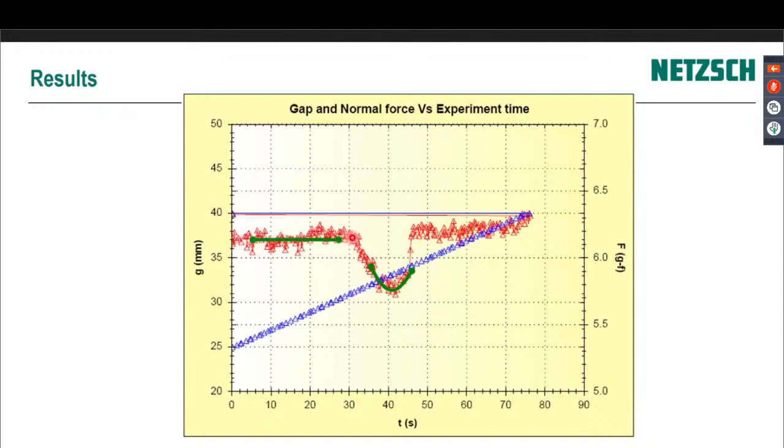And then as it lifts out of the liquid, it starts to lift a meniscus. And then it gets high enough and then it snaps. So now the Du Noüy ring is outside of the liquid. This is as it's coming up, it's lifting a meniscus.